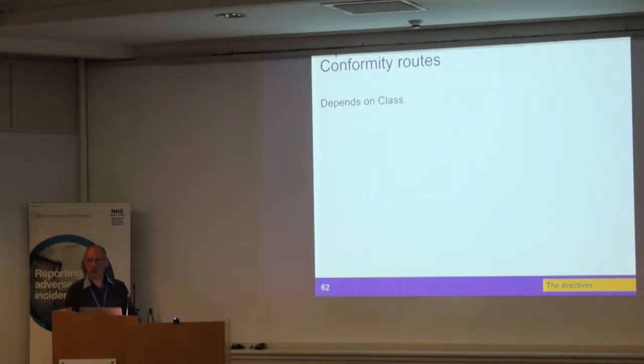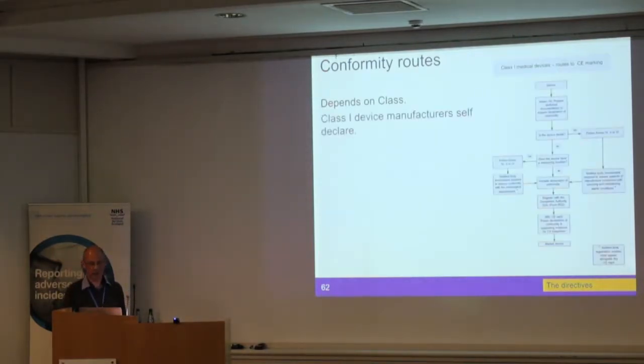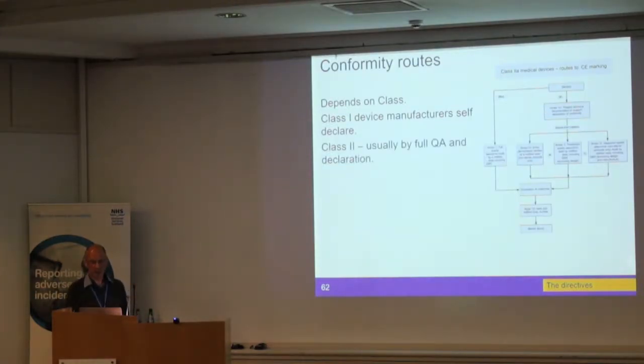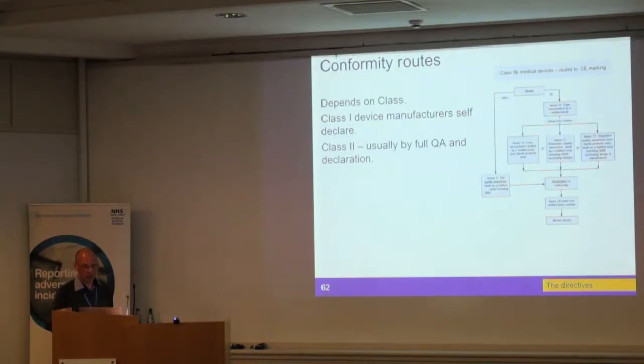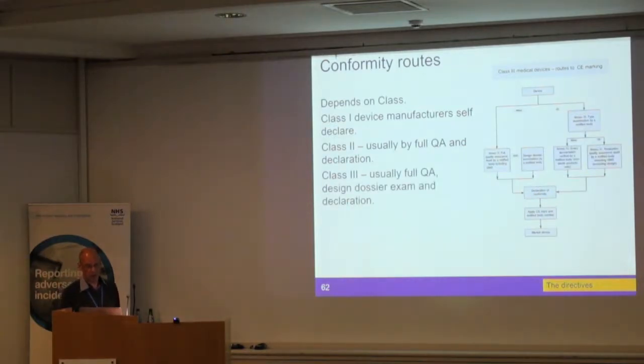Once you've got the classification of your device, you will follow a conformity route, and again that depends on the class of the device. For class 1 device manufacturers, they self-declare that the device is fit for placing on the market. There will be notified body involvement if their software has a measuring function, or, strangely, for sterility. For class 2 devices, the manufacturer would usually follow a full quality assurance route. For class 2B and class 3, there will be full QA, a design dossier exam by a notified body, and a declaration.